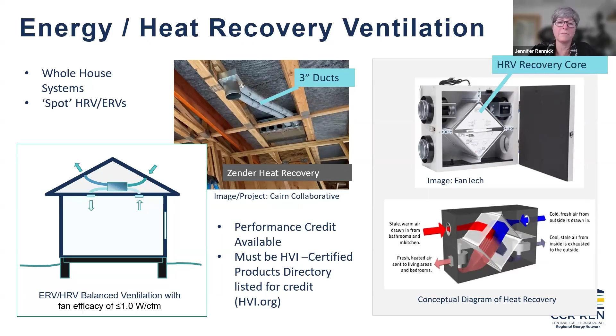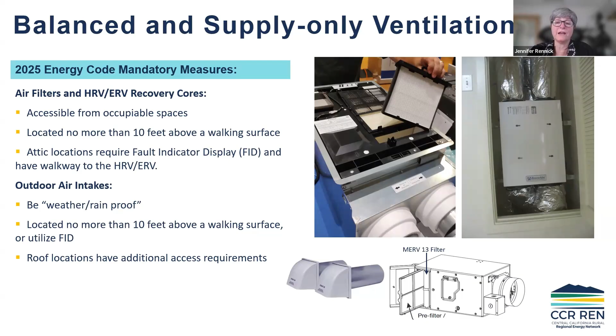And then from a code perspective, there are some new mandatory measures that are specific to the HRV and the ERV. And even now, some of what might seem like common sense things had to be put into the code because of how these were installed. So, for example, the outdoor air intakes have to be weather and rainproof covered. Seems like it makes sense, but it wasn't happening, causing issues, et cetera. And then also fault indicator displays need to be there, and homeowners need to have access to these units so they can change the filters in them.